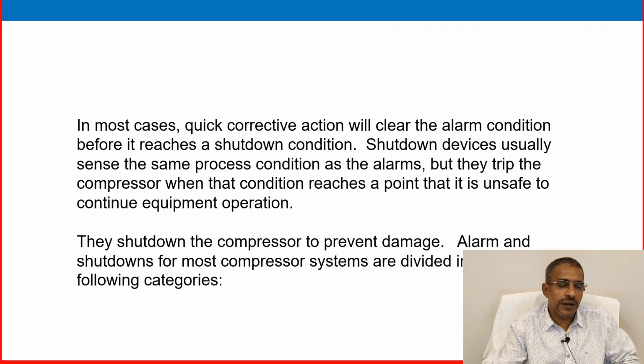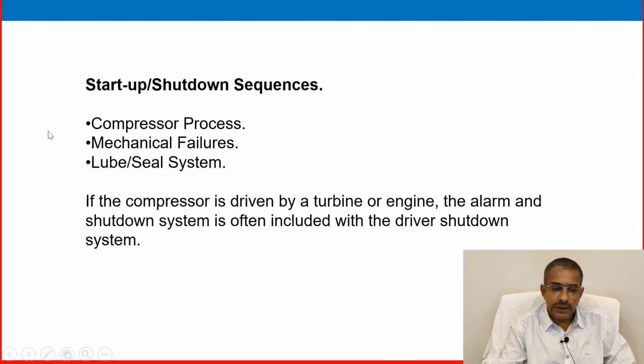That is the main difference from an alarm. An alarm will annunciate with various sound and visual effects in the central control room, and an alarm will not take any action. But a trip is not like that. A trip condition will annunciate the message, but it will take an action as well. It shuts down the compressor to prevent damage. Alarm and shutdown of most compressor systems are divided into the following categories: compressor process, mechanical failure, and lube or seal oil system. In these areas, most of the alarm and shutdown or trip conditions are provided.